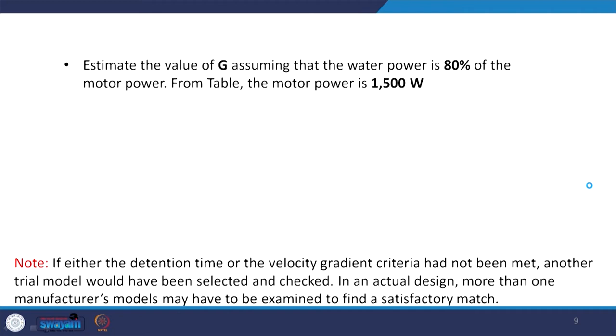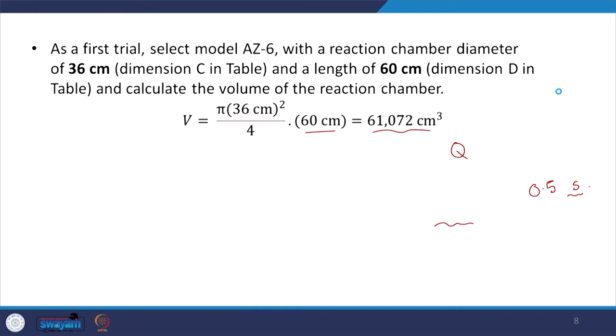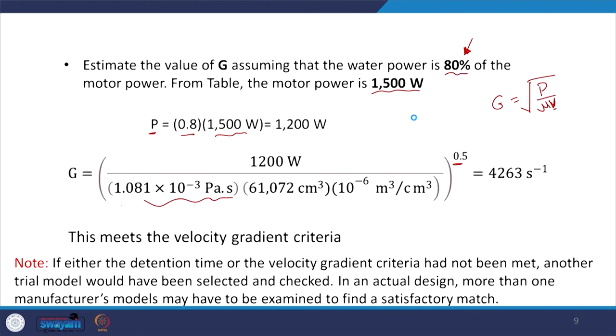Next we need to look at G. We are assuming that not all the energy from the 1500-watt rated motor power is transferred to the water — we assume efficiency is around 80%, so effective P is 0.8 × 1500 watts. G equals the square root of power divided by mu times V. From that we get the G value, which gives us an idea about the mixing. This is acceptable since we were looking at 3000 to 5000 for adsorption coagulation.